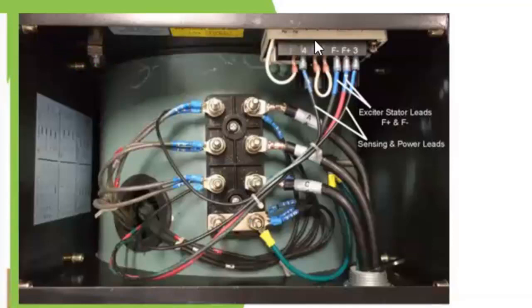Okay, so this is the positive terminal from the AVR. This is the AVR, okay, this is the positive terminal, and this is the negative terminal. So which means that we have DC voltage coming out from the AVR, and this one, black and red, are sent straight to the exciter field, the one on that stationary part of the stator cover, on the generator stator. So now this one feeds straight to the exciter field.